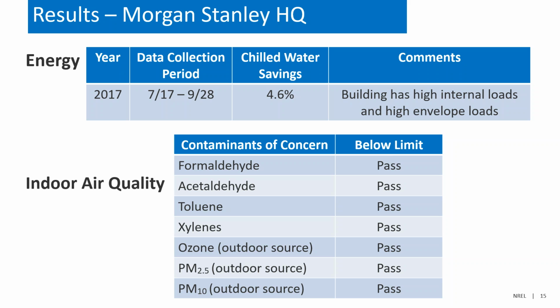But we saw about a 4.6% chilled water energy savings, which may not sound like a lot, but because it's a large building, it's a very high cooling load, and it's really dominated by the high internal loads because it's a high occupancy building with a lot of computers and other internal loads and plug loads. And then this is a large glass high-rise building in New York City, has very high envelope loads as well. So those are really the dominating factors for chilled water cooling load in this building compared to the outside air load in the building.